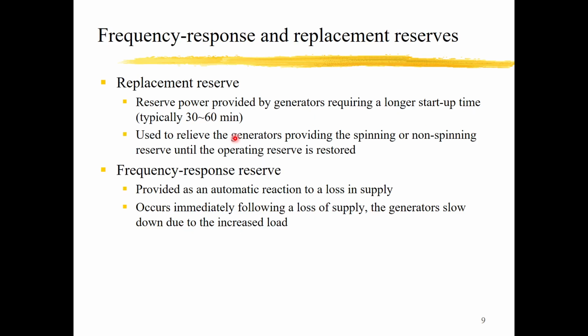And then I'll talk about what those reserves are. First is the slowest one, the replacement reserve. The replacement reserve is the reserve power provided by the generators. Okay, they can only be provided by generators, and these generators need a longer startup time, like 30 to 60 minutes.